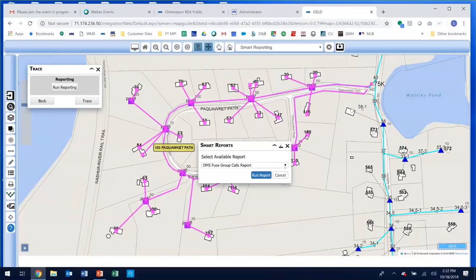Beyond looking for overloaded transformers, when he first got the system he'd check for overloads in spring, anticipating the summer heat wave. Then in the fall he started using the system to scrub his data looking for anomalies. One example I always remember: he found a 30-unit senior housing apartment building that, for some reason, had a 300 kVA transformer sitting there at only 4% load during peak. He put that transformer back into inventory so next time he needed a 300 kVA, he'd have one ready. This reduced his capital costs and reduced no-load losses because the system became more balanced, all without heavy investment on his part.